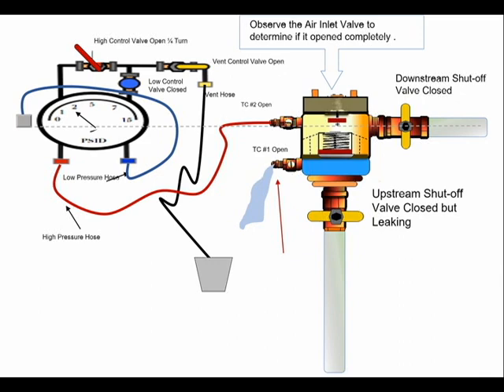To test the air inlet valve opening point with a leaking upstream shutoff valve, follow the procedures for measuring the opening point of the air inlet valve as previously stated. But before opening the test kit high control valve one quarter turn, slightly open test cock number one.